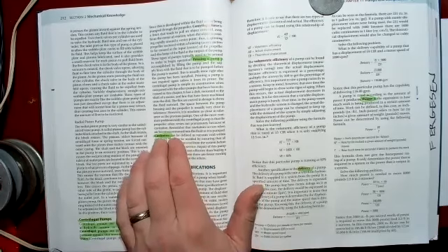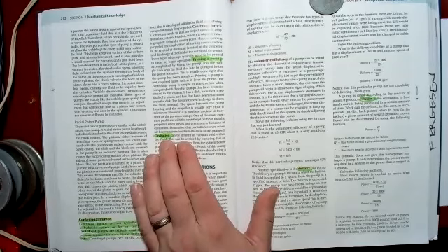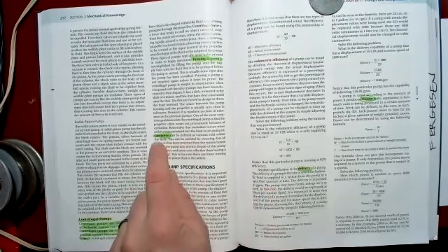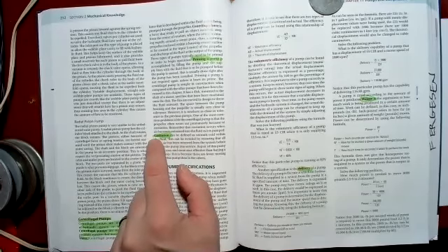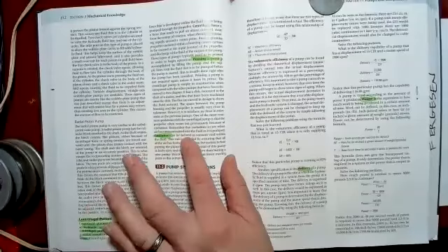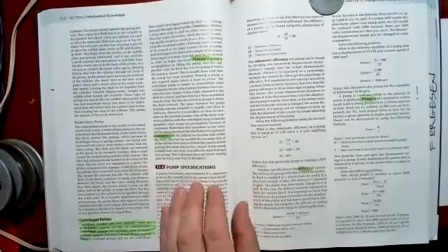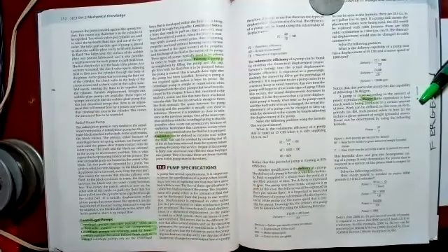And they can actually destroy a steel impeller because there's so much power involved in these little vacuum explosions. So you can create cavitation by having too much back pressure, by having clogged filters, and a variety of other things. If you do have a cavitating pump, you need to shut that pump down as quickly as possible.